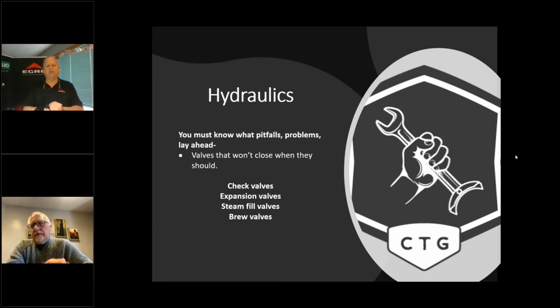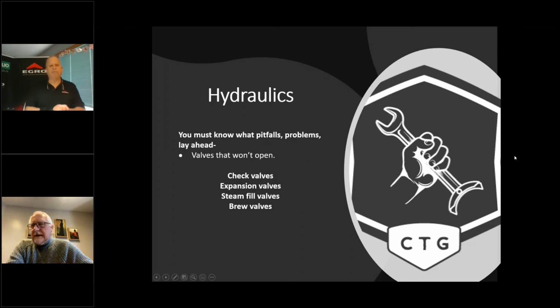And how many times back in the day, and probably even still to this day, there's a certain brand of machine where they used to put the check valve at the pump, and then the technician would come out, change the pump, and not put that long thing back on, and then all of a sudden you're diagnosing three different problems over the next two months, right? As you're heating pumps for a living. Yeah, my water line's hot. What the hell?